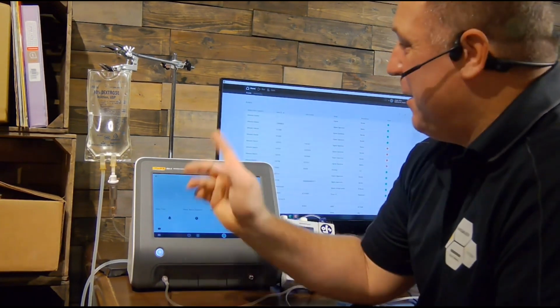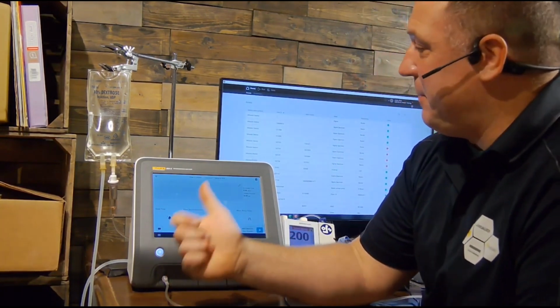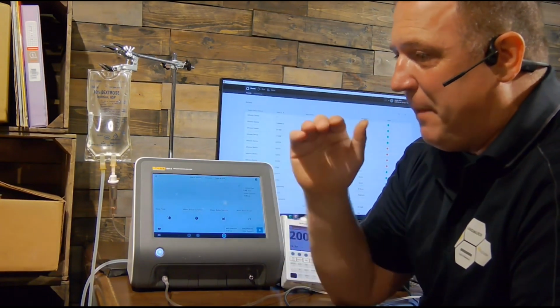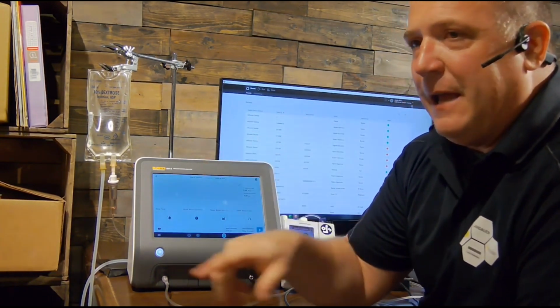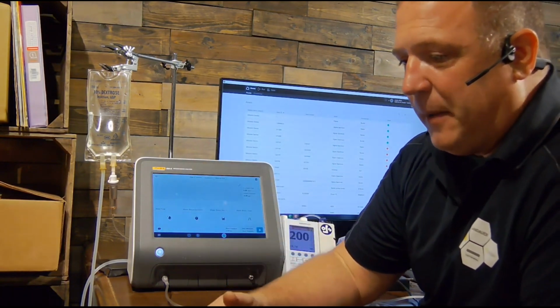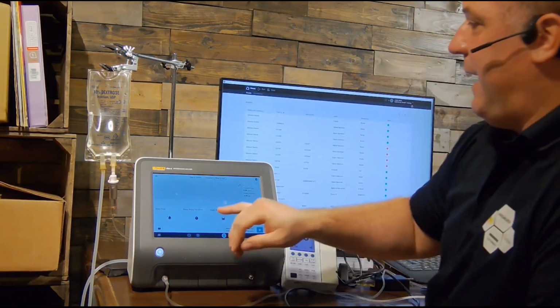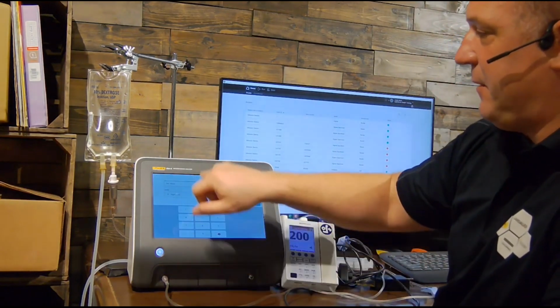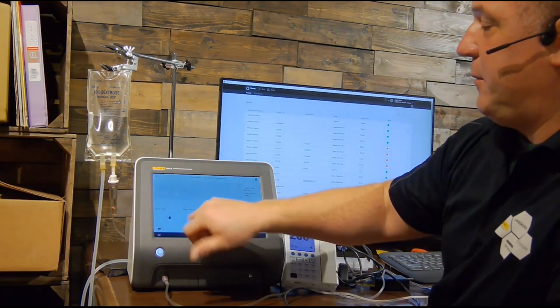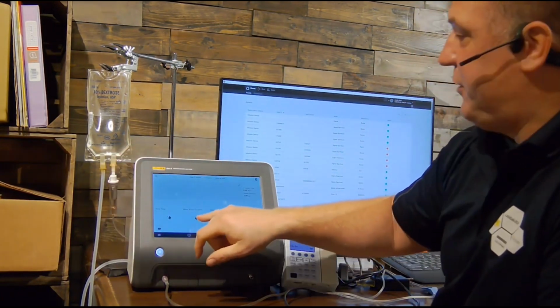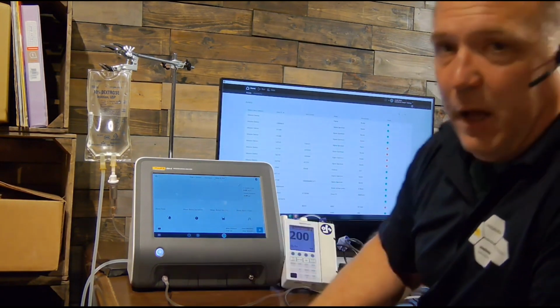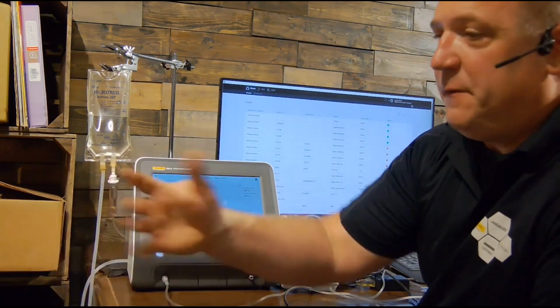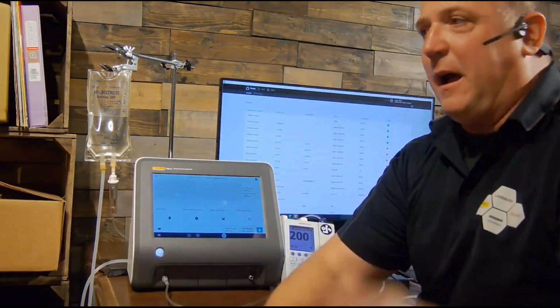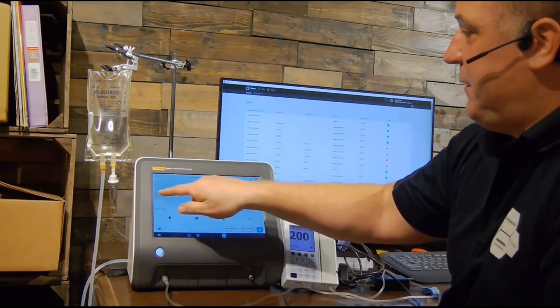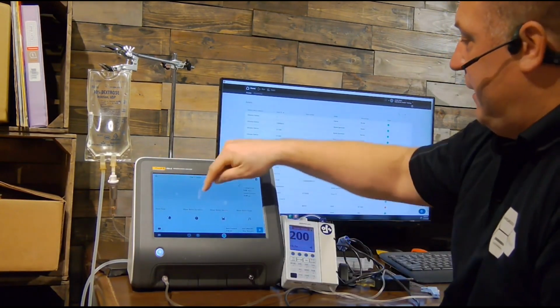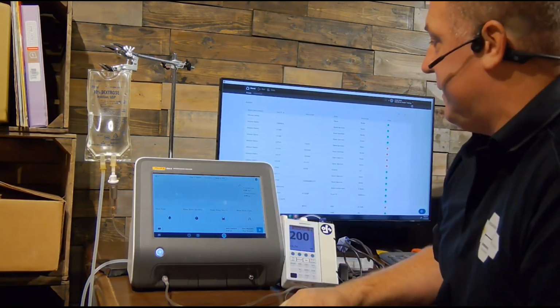Here's one I love: bolus and PCA. I used to do a lot of pain pumps and PCA pumps, and it was really difficult to measure that bolus flow, especially since many require 10, 15, or 5 to 10 different titrations that you then have to average. With the IDA-6, you can program your base flow, say 5 milliliters an hour, then hit bolus and it measures your bolus duration, volume, and flow. You can do 3, 4, 5, 6, up to 15 of those, and it averages them together, discarding the high and low readings. You'll even see a baseline with your square boluses. It's a really nice feature, and it's very accurate.